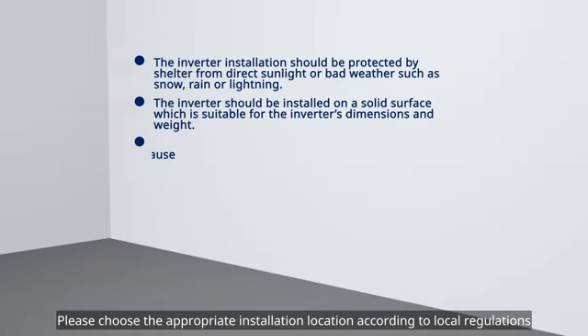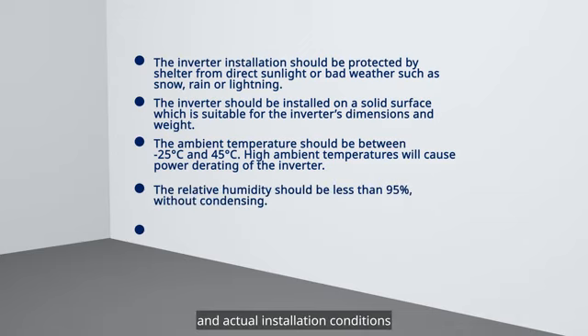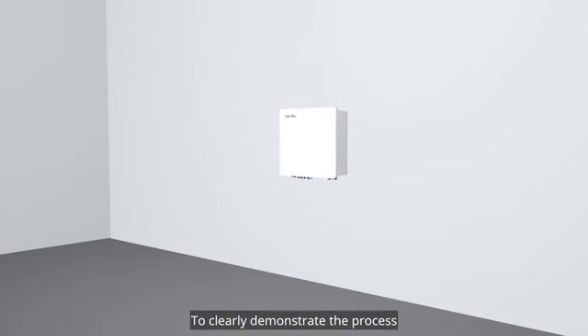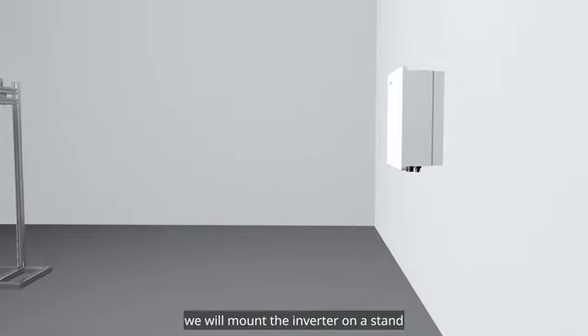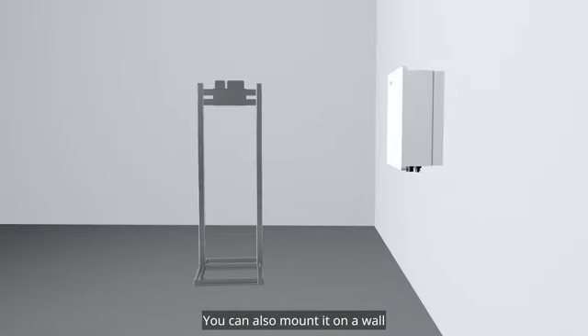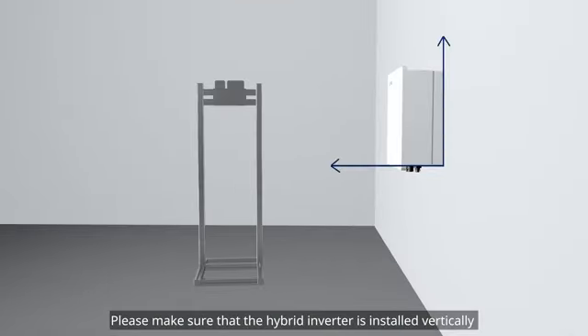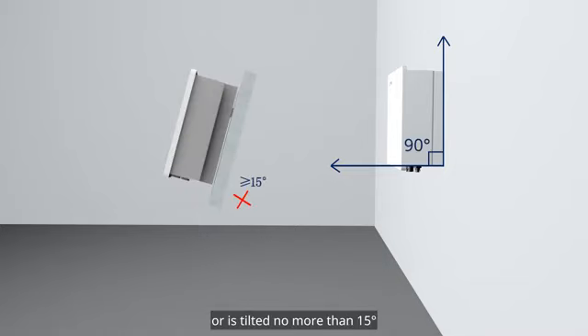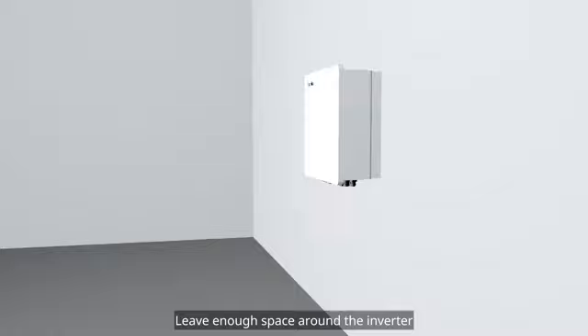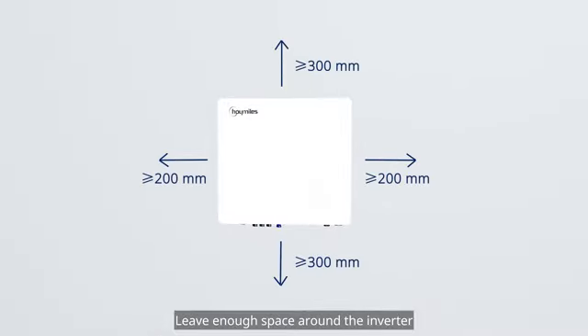Please choose the appropriate installation location according to local regulations and actual installation conditions. To clearly demonstrate the process, we will mount the inverter on a stand. You can also mount it on a wall. Please make sure that the hybrid inverter is installed vertically or is tilted no more than 15 degrees. Leave enough space around the inverter.